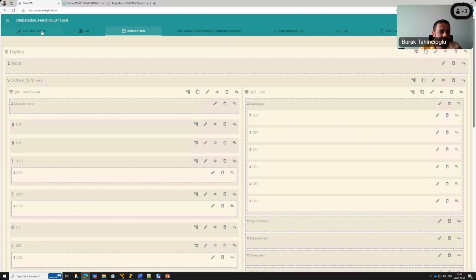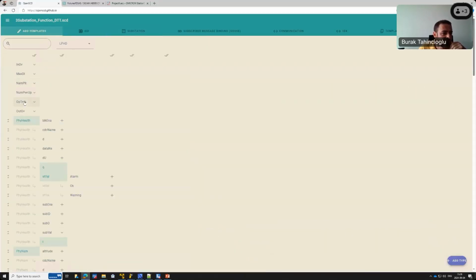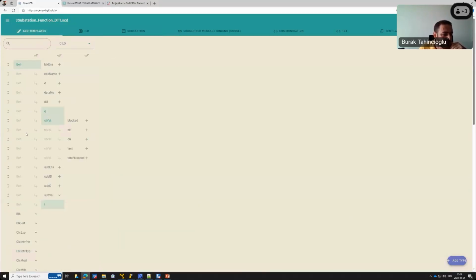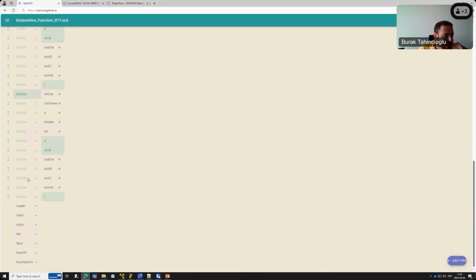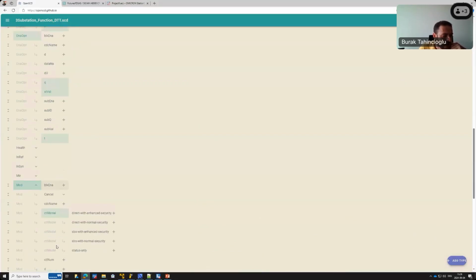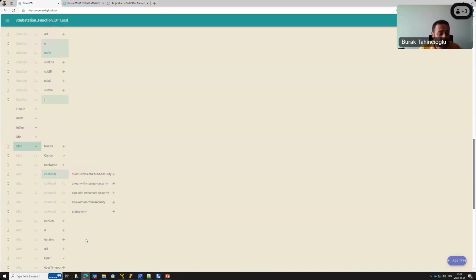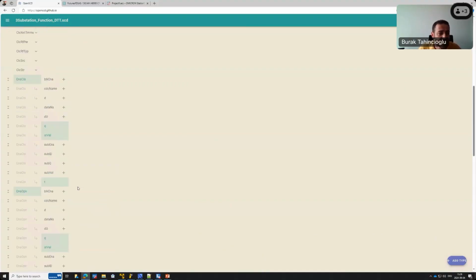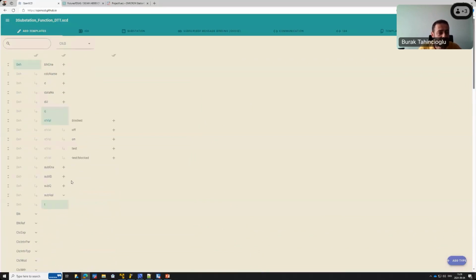How can you do this? You go to OpenSCD and in the add templates, and here you would select the mode, so for the CILO, if I would like to have the mode, I would just need to enable it from here. Then I would have a mode. So as I said, mode can be controllable or not controllable, but the resulting behavior is a combination of different modes in the root logical node, but I don't want to go into details for that.